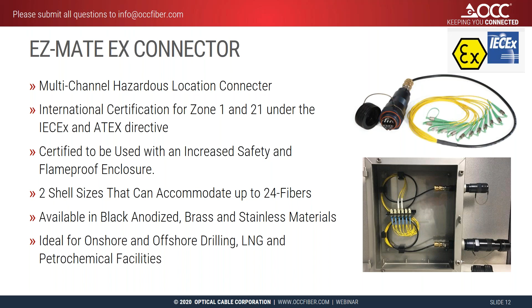We are certified for use on 2 enclosures: the increased safety enclosure, shown in the picture, and the flame-proof enclosure, which is much larger and more robust. It comes in 2 shell sizes - the smaller handles 4 to 6 fibers, and the larger handles 12 to 24. We've used these in walking rig applications where the drill head had to be moved several times during a drill, allowing disconnect and reconnect within the hazardous zone. These are available in the 3 materials we discussed earlier: black anodized, brass, and stainless steel. They're ideal for onshore and offshore drilling applications, as well as liquid natural gas and petrochemical facilities.